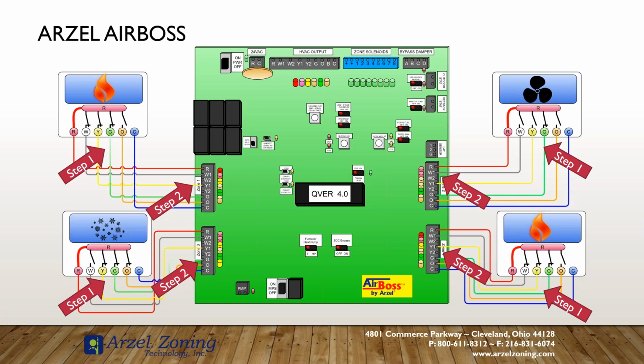So on this image, there are 2 thermostats in heating, 1 thermostat in cooling, 1 thermostat in fan. That's to show that you can have thermostats with dissimilar calls, but the panel plays the coordinator. And as a coordinator, it determines what takes priority, heating, cooling, or fan. Well, in this case, fan, doesn't matter what panel of ours you have, fan is always the least priority. So we pick between heating or cooling based on your operation.